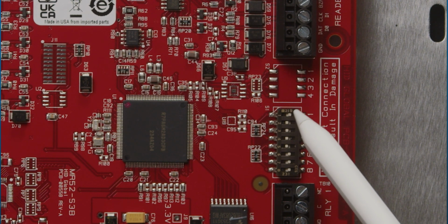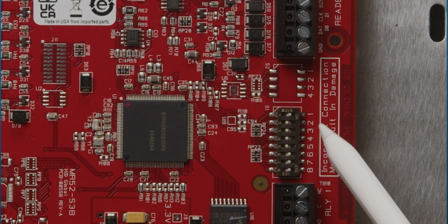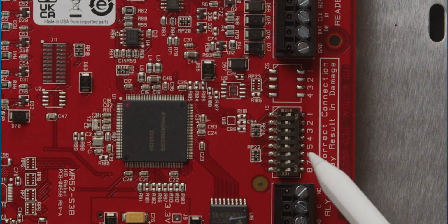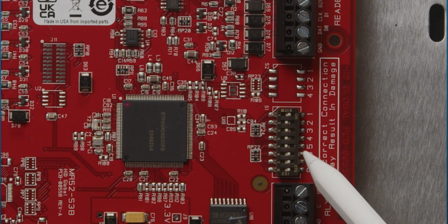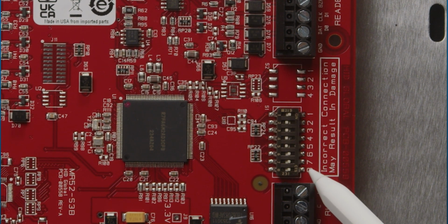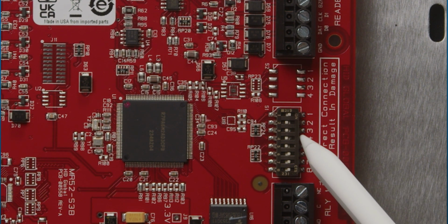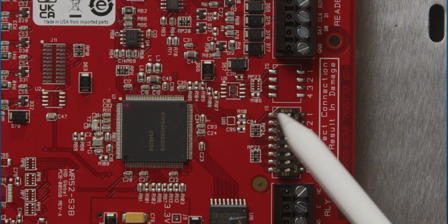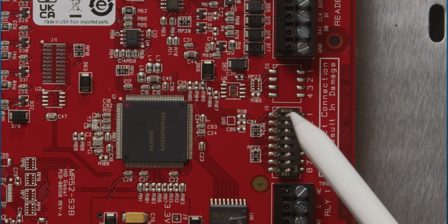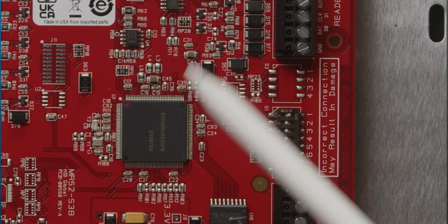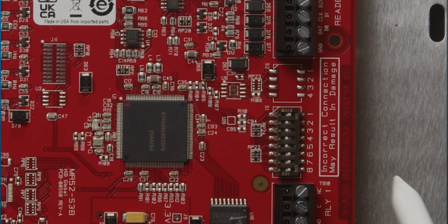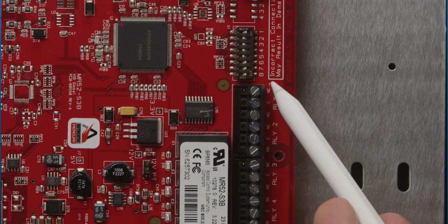For example, pin 1 being on, that's address 1. Pins 6, 7, and 8 are also on. That's for our baud rate. So 6, 7, and 8 will be on with every MR52 that's down line. The address terminations will obviously change. For address 1, it's 1 on. For address 2, it's 1 off, 2 on, just as an example, but we have a whole knowledge base about that. We also have our outputs.